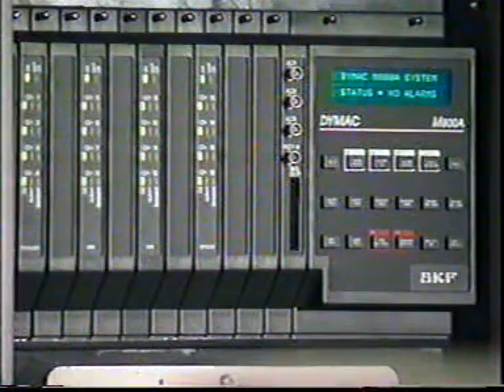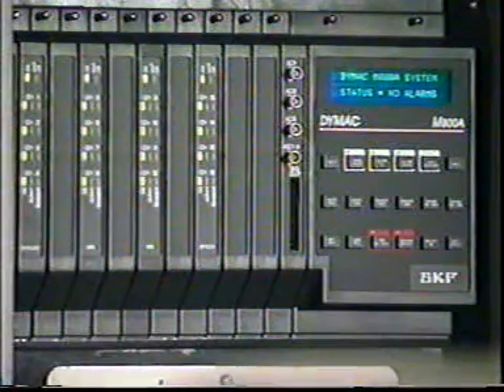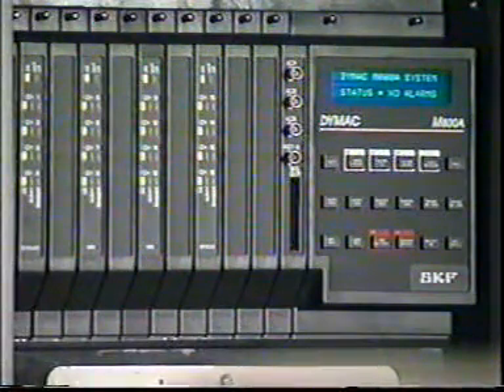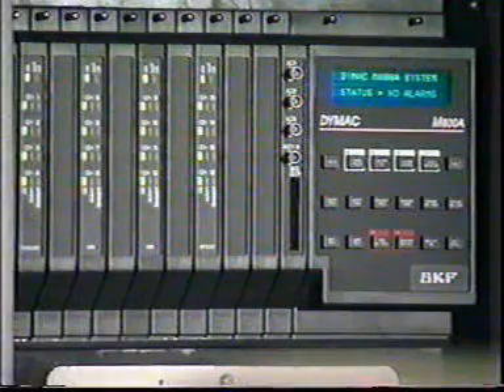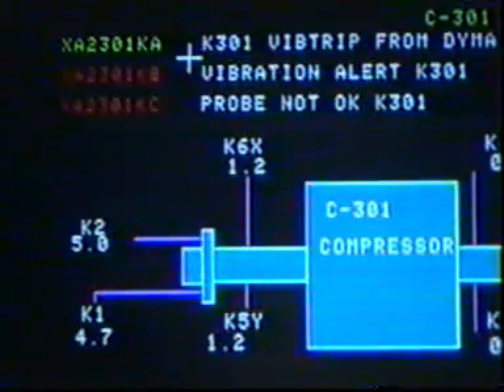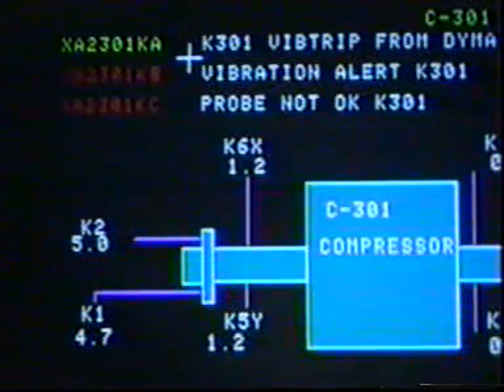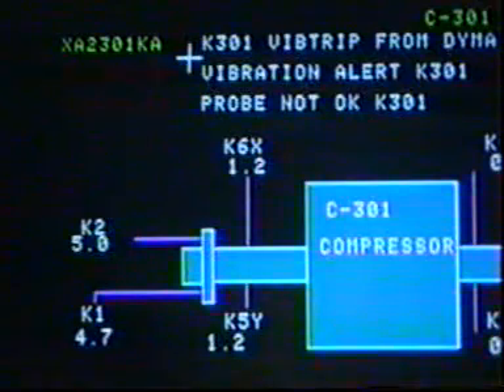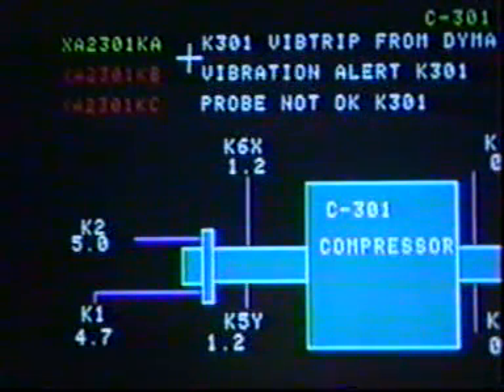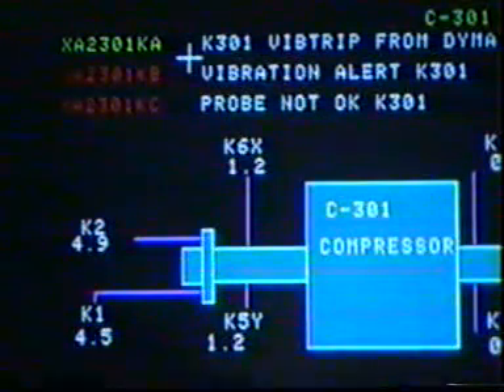Some permanently installed systems will provide self-diagnostics. This can show the operator or technician that a particular channel has lost its monitoring capability. This indication may only tell you that the channel is not functioning properly. Troubleshooting will be required to properly identify the source of the problem. Consult your manufacturer's instructions for troubleshooting charts and guidelines.